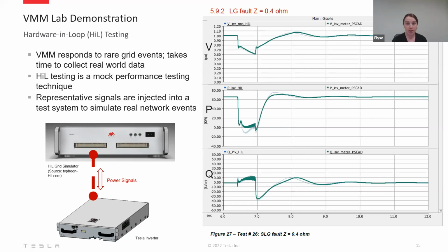In that case we would see a certain voltage signature on the network, which is the injected power signal into the inverter. The purpose of the HIL test is to show physically how the inverter responds to such a condition, and then apply the same condition to the model to validate that our models accurately predict the real hardware's response. In that graph, you can see there's a blue line for the actual lab test results and the green line for the modelled results. This is a really close match, which is a good result.